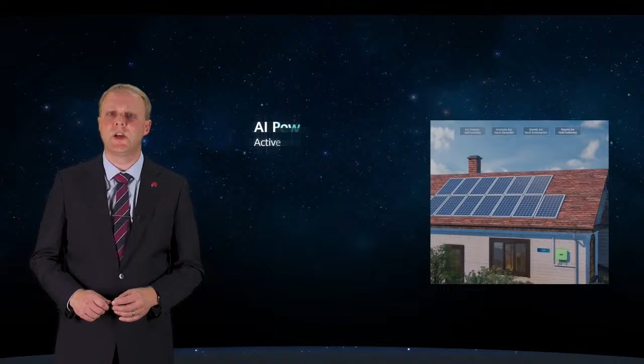When a real potential arcing risk occurs, via its local neural networking algorithm, the system can accurately detect and judge whether it is a real or false alarm. When a real arc is detected, the inverter will shut down immediately, extinguishing the arc as well. The entire process, from detection to system shutdown, takes less than half a second, well within the standard requirement of 2.5 seconds.